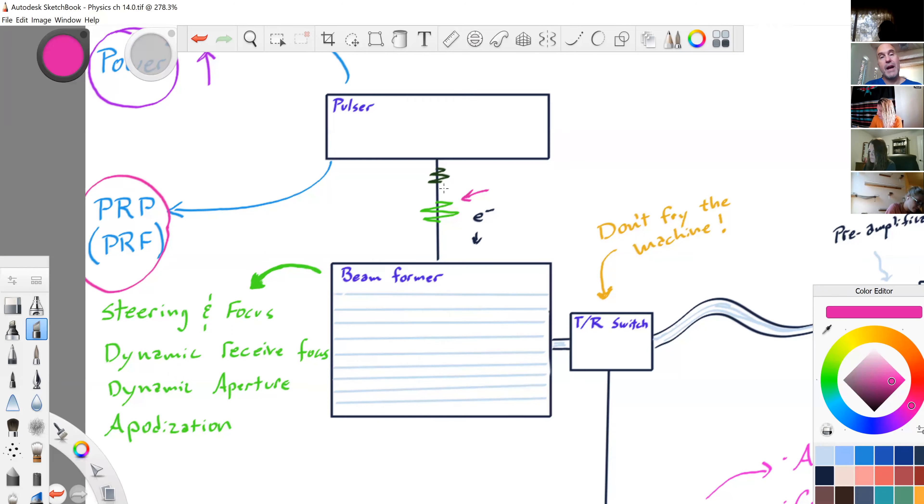In color, we have direct control of the pulser through the PRF button. In grayscale, depth changes the PRF — the engineers have already figured it out for us, setting the PRF automatically at 5 cm, 10 cm, etc. In color, the pulse repetition frequency is Doppler only — you're not changing the grayscale background PRF, only the color or spectral. And that, for complicated reasons, changes our scale.